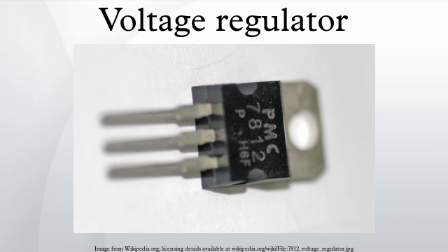Some units have included redundant capacitors to allow several capacitors to fail between inspections without any noticeable effect on the device's performance. Output voltage varies about 1.2% for every 1% change in supply frequency. For example, a 2 Hz change in generator frequency, which is very large, results in an output voltage change of only 4%, which has little effect for most loads.